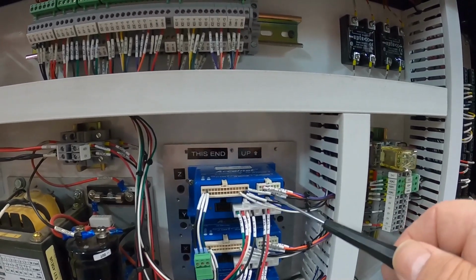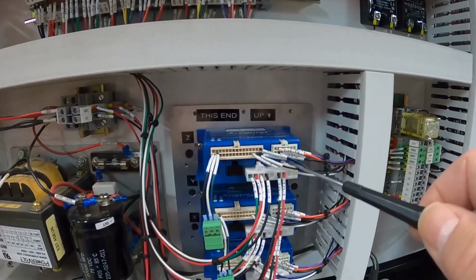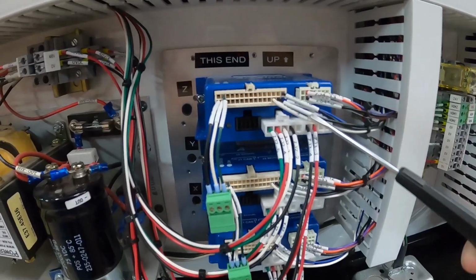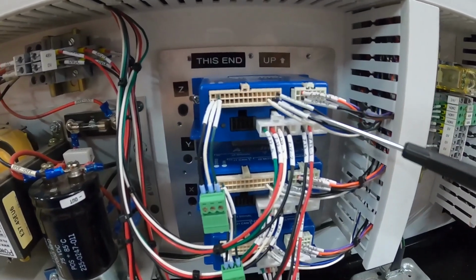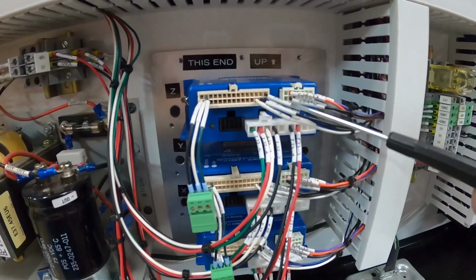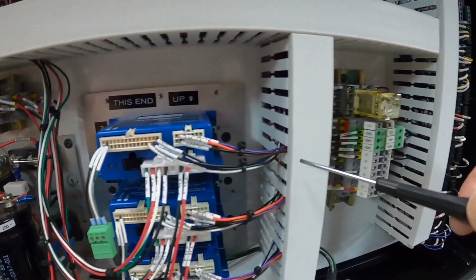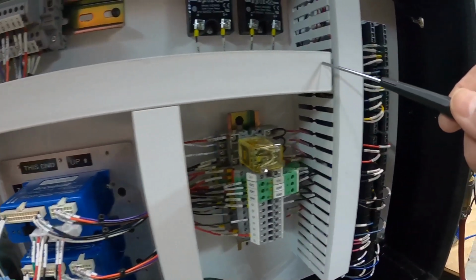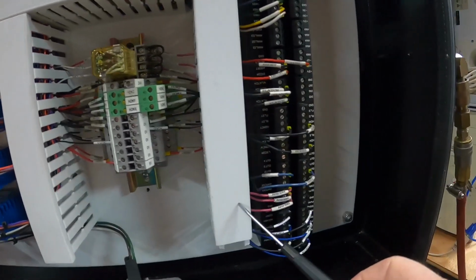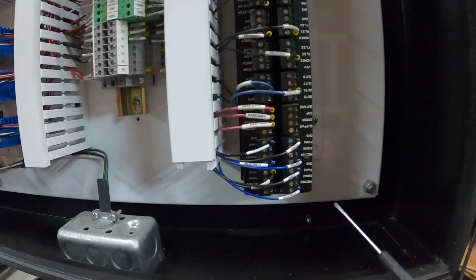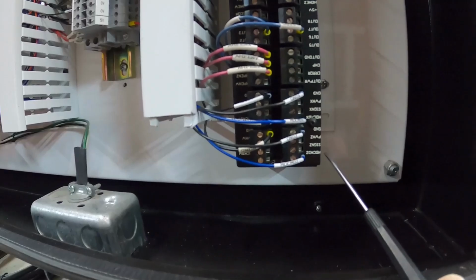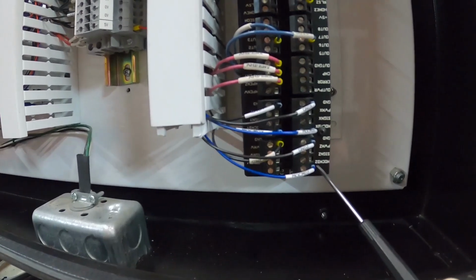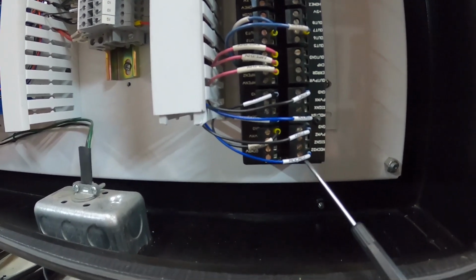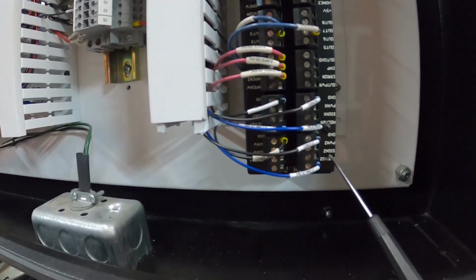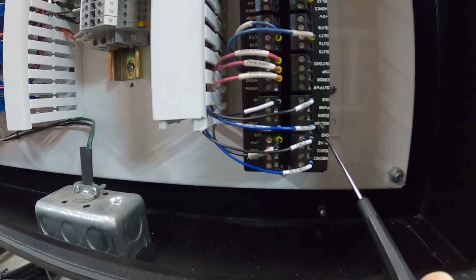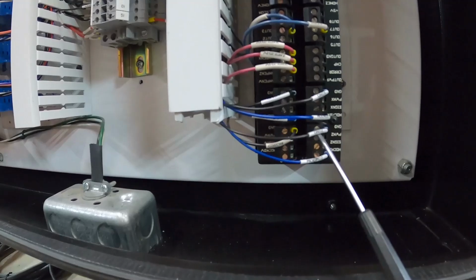As I said, there's a 0 volt and a control line right here. 1 is the control line and 16 is the 0 volt line. They run over here, down here, and to the ICM 1100. You see this says motor command Z, and that's the blue line. And then there's a ground connection, and that's the 0 volt line.